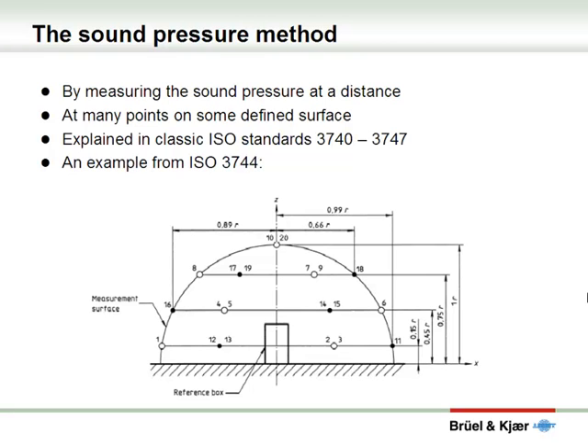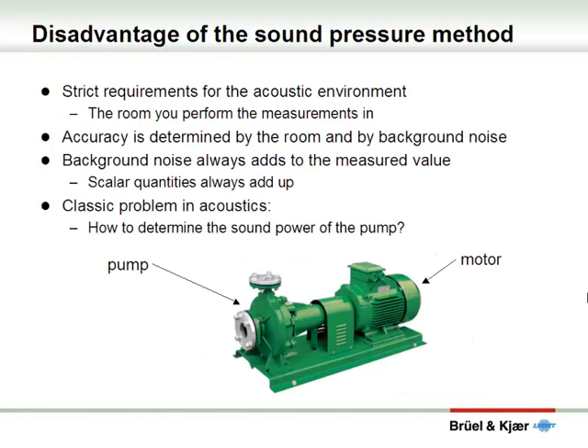For a long time sound power has been determined using sound pressure measurements. What that means is you place your source on a horizontal surface and place microphones on a hemisphere at a large number of points. Measurements of this type are clearly explained in classic ISO standards in the range 3740 to 3747. The picture shows an example from the standard ISO 3744. Determining sound power using the sound pressure method has a number of disadvantages. The room must be strictly controlled. The acoustic properties of the room and the background noise will influence the accuracy of your measurements. Because sound pressure is a scalar quantity, sound pressure levels always tend to add up, so any background noise will add to your measurements and cause an overestimation of the sound power.